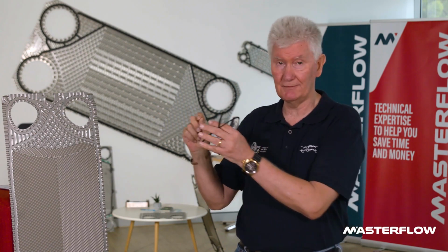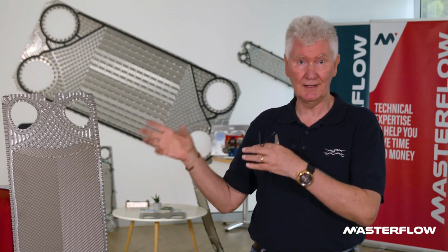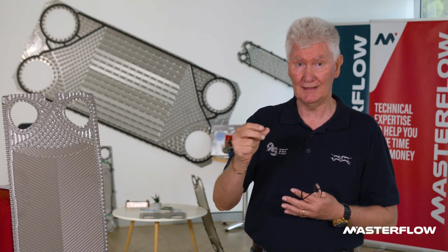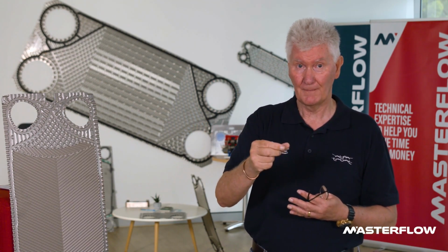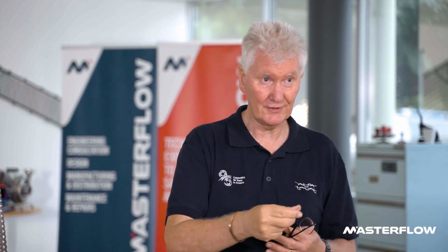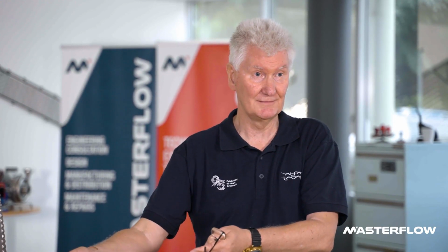Okay, so if you have the right geometry, and this is where Alfa Laval to some degree has a real benefit, on some of our medium to large heat exchangers we have 3 channel gaps: 2.5, 3 and 4. If you have low pressure drop, you want a larger gap. As you increase the gap, your turbulence decreases, your pressure drop decreases, but you pay for an increased area.